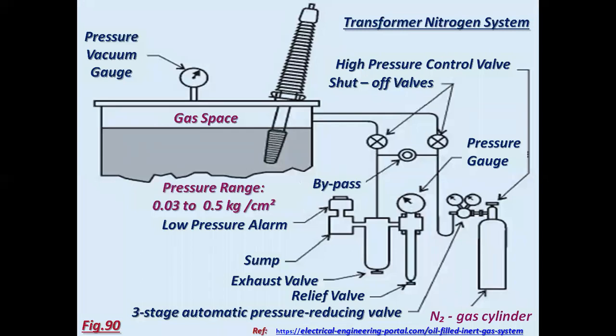See the diagram, nitrogen system in the transformer. Pressure vacuum gauge, gas space, pressure range 0.03 to 0.5 kg per centimeter square, low pressure alarm, bypass valve, pressure gauges, sump, exhaust valve, relief valve, 3-stage automatic pressure reducing valve, and nitrogen gas cylinder.